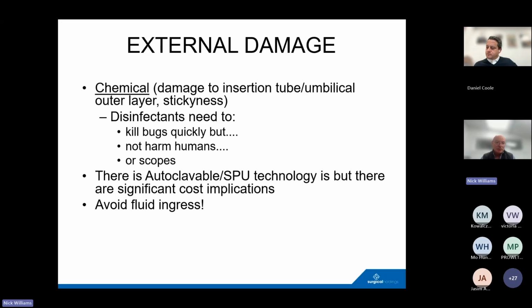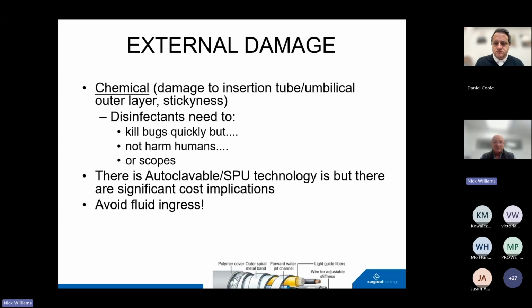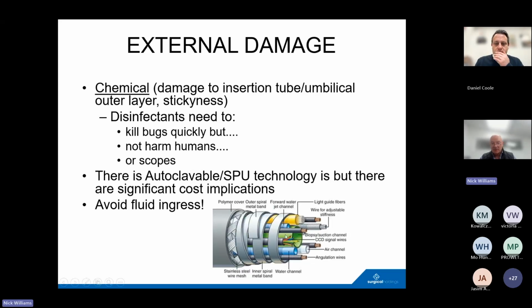So, in general, you're talking high level disinfectant usage with a state-of-the-art expensive instrument, and it's important to avoid fluid ingress because that's costly. If you remember this picture, if you've got a laser fiber going through there, firing, and you get a hole in the biopsy suction channel, and you then put it through a cleaning process, the disinfectants will get internally. You've got fluid ingress, and if that then gets to the CCD or the CMOS chip and blows it, you're talking about very expensive repair, thousands, maybe over 10,000 in some cases. So you obviously want to avoid that.